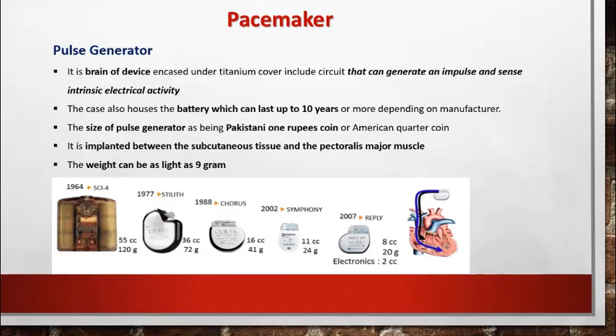Then the leads, you can see these. Leads are insulated wires, 1 or 2, that connect the electrodes to the generator. They pass through the central vein, with the aim of positioning the tips against the myocardium of the targeted chamber. The leads propagate stimulus from the generator to the heart and relay intrinsic myocardial signals back to the generator. Then the electrodes are located at the tip of the leads. You can see these are the tips of the leads. Electrodes are there. They are positive and negative, anodes and cathodes. The voltage propagated along the leads depolarizes the myocardium, generating an impulse. These electrodes also function as sensors by recording intrinsic electrical activity.